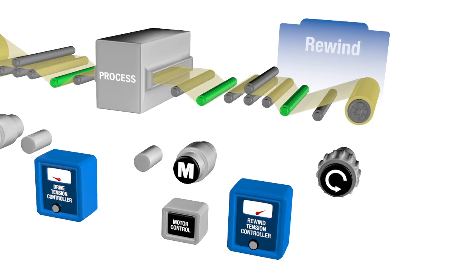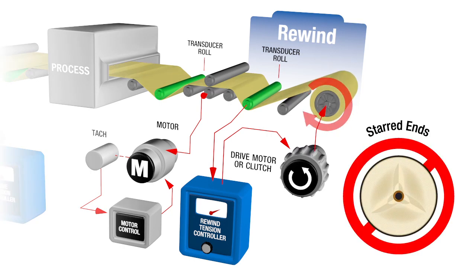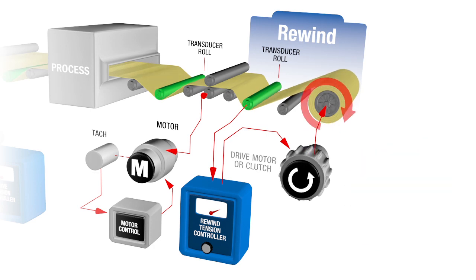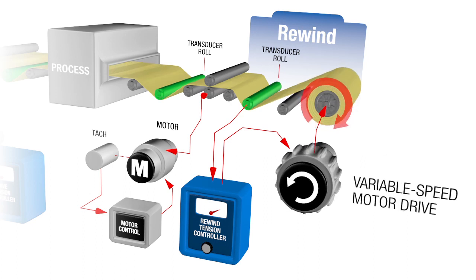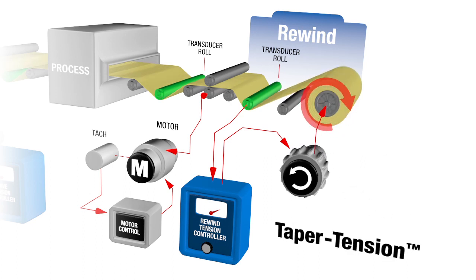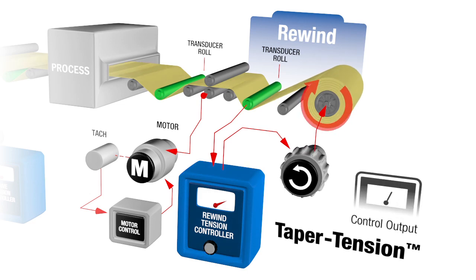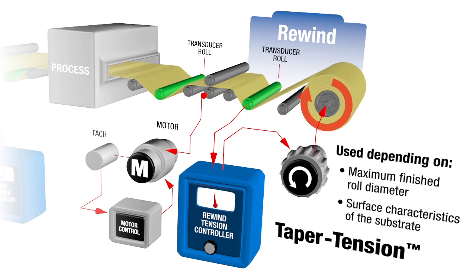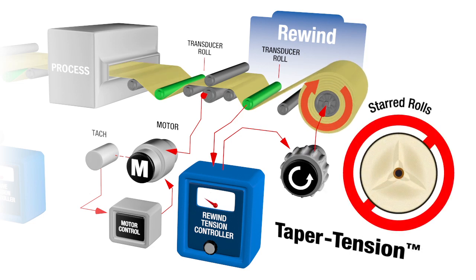Proper rewind tension control is essential to winding a consistent, unflawed roll, and to prevent starred ends, telescoping, or offset edges of the finished wound roll. The tensioning device to be controlled is usually an electric clutch or a variable-speed motor drive. Taper tension, a feature of the rewind controller that causes its control output to gradually reduce as the roll builds, is used depending on the maximum finished roll diameter and surface characteristics of the substrate being wound. Winding with taper tension reduces the incidence of telescoping and starred rolls.